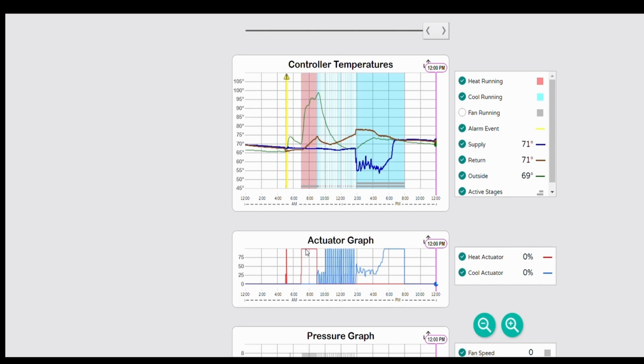The heat actuator is broken. It does not open when you think it's supposed to open. Because this is telling you that it's calling for it to be open. It doesn't actually mean that it is all the way open. So then, it could be backwards. So when you send it a 100% command, it goes to 0%. Could be backwards. Or also, I think in this case, the boiler was not on.